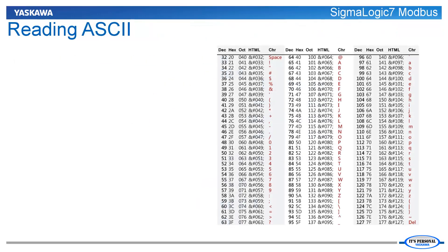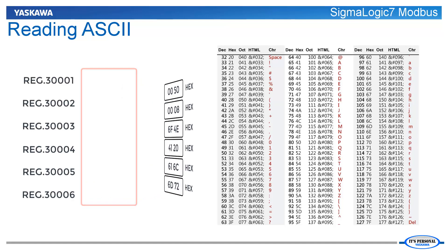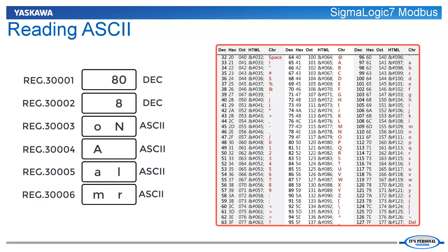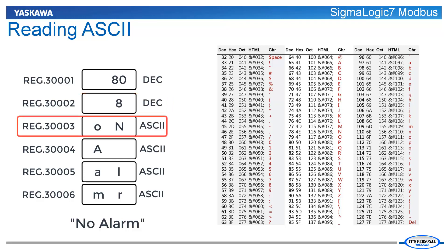The Sigma Logic 7 Modbus alarms are transferred as ASCII data starting at input register 30001. Each ASCII character is represented by a byte of information, so two characters will be placed in each Modbus register. The user will need to employ an ASCII lookup table to convert each character and then concatenate them into a complete string. There are many free ASCII tables available in the public domain to help with this conversion. The length of the alarm string can be found at register 30002, and the characters begin at register 30003.